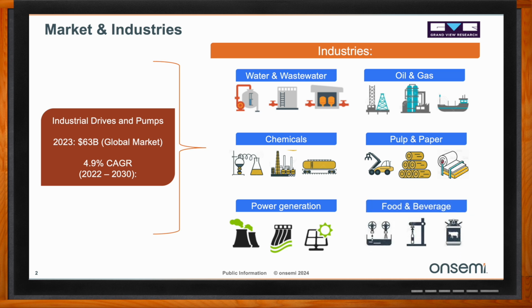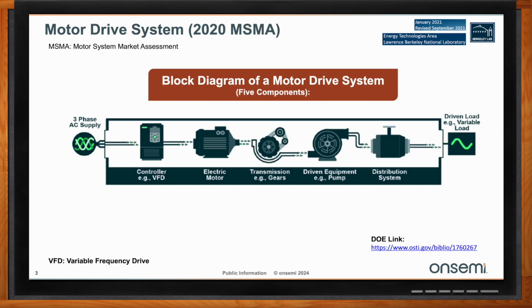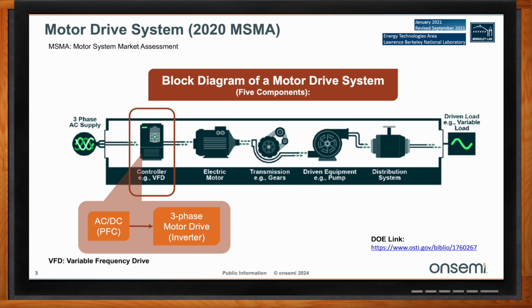The Department of Energy, in cooperation with the Lawrence Berkeley National Laboratories, came out with the 2020 MSMA, the Motor System Market Assessment, where for the United States they divided the industrial drives and pumps into a block diagram of 5 components. The first is the controller, or variable frequency drive, which has AC to DC conversion and a 3-phase motor drive inverter. The second component is the electric motor. The third is the transmission or gears. The fourth is the driven equipment, being the pump or blower. And finally, the fifth component is the distribution system.